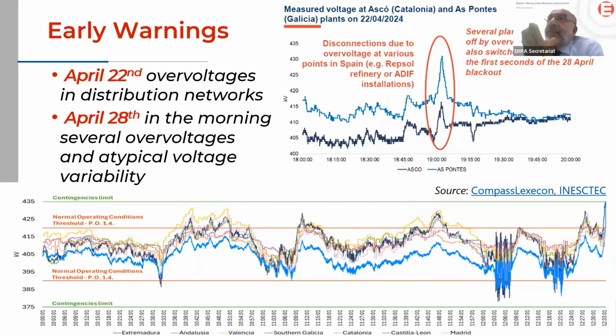Before the event, interestingly, there were some warnings - not only on the same day but also some days before. Distribution networks connected to the Spanish system were impacted by over-voltages. The voltage in the distribution system depends on the voltage in the transmission system, so if there is an over-voltage in the distribution system, it means something is not going well in the transmission system from the viewpoint of voltage.